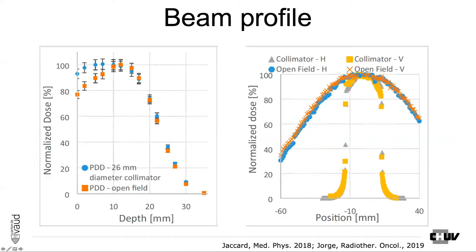During that time, also at the beginning with that prototype, we performed the medical physics duties of characterization: beam profile, PDDs, which were also published. This allowed us to do biological experiments with a certain confidence in the dose distribution.